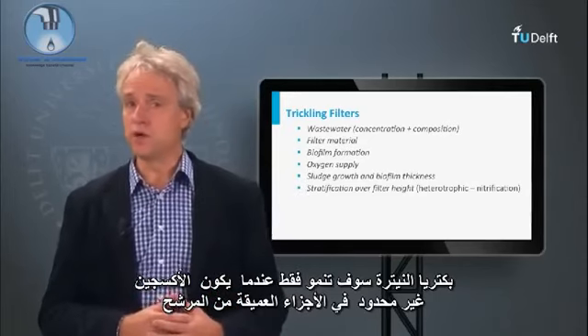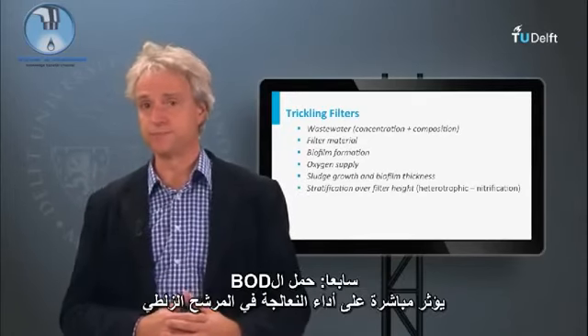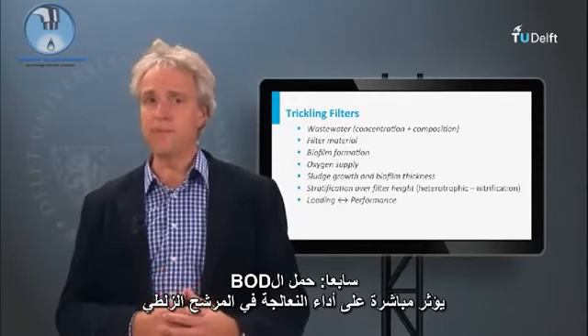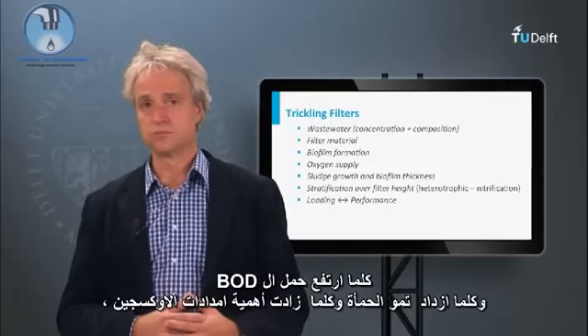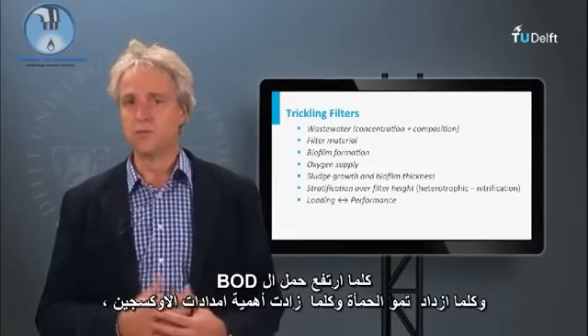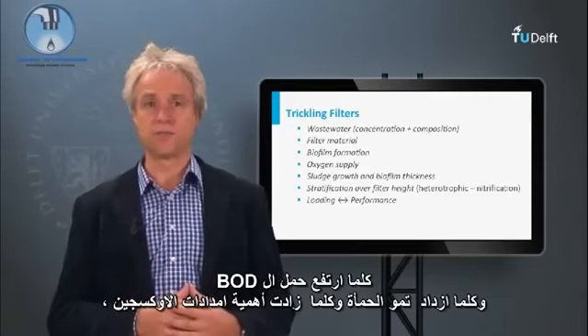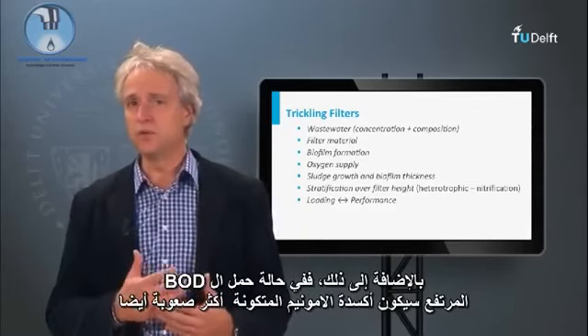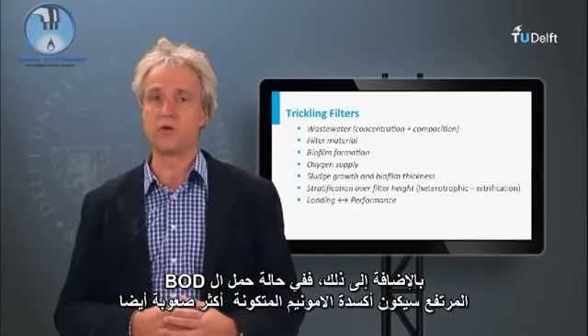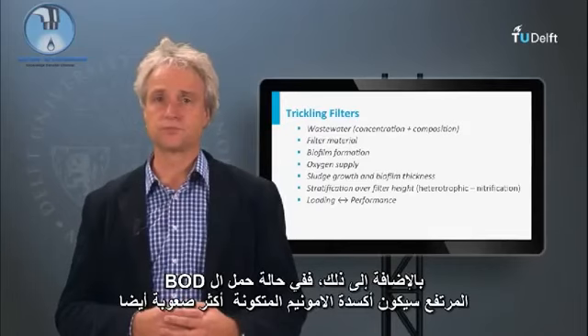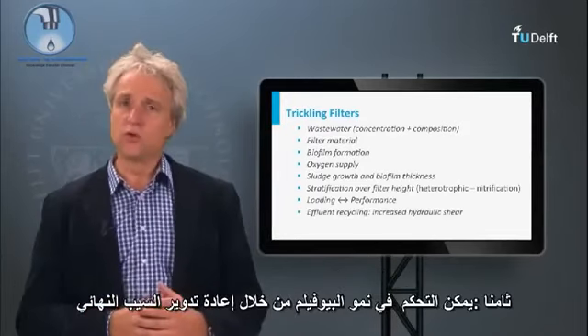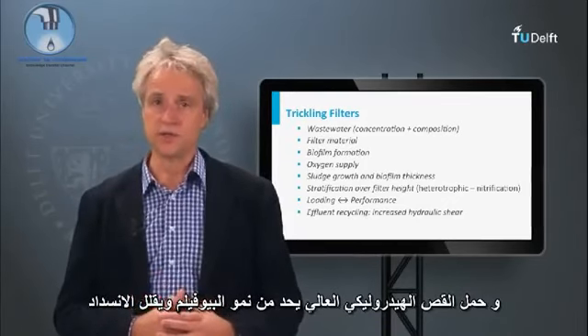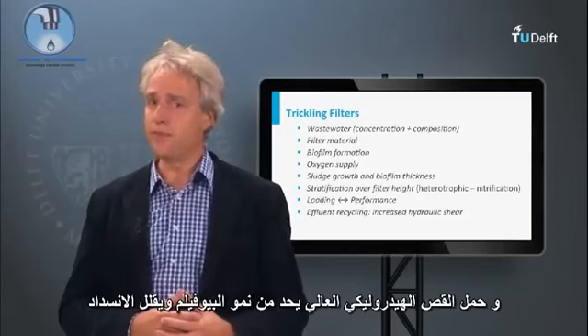Nitrifiers will only grow when oxygen is not limited in the deeper parts of the bed. Seven, the applied BOD loading will immediately impact the treatment performance of the trickling filter. The higher the BOD load, the more sludge will grow and the more crucial the oxygen supply will be. In addition, at a high BOD load it will be more difficult to also oxidize the formed ammonium. Eight, biofilm growth can also be controlled by applying effluent recirculation. A higher hydraulic shear limits the biofilm growth and minimizes clogging.